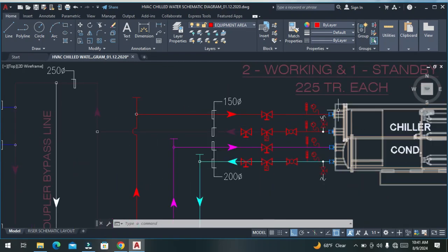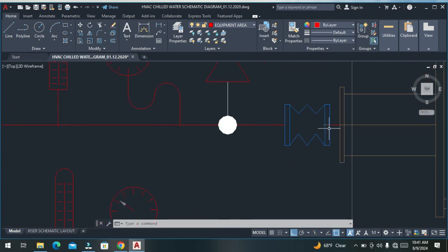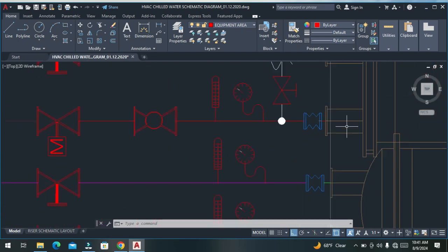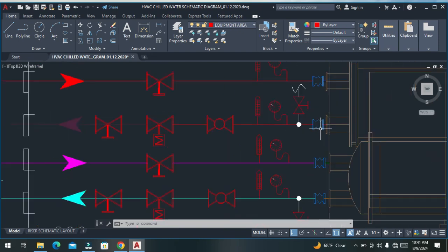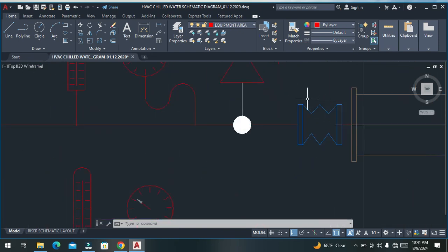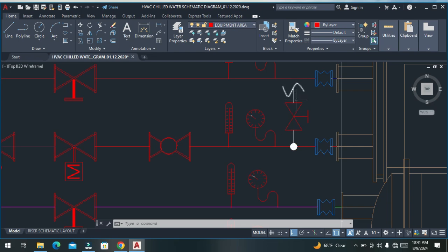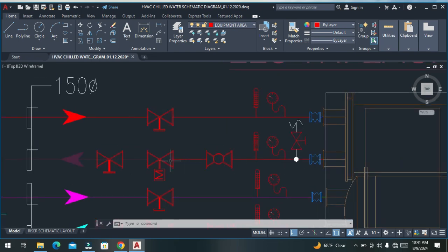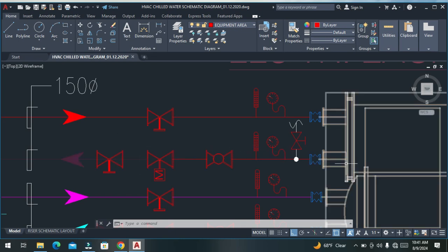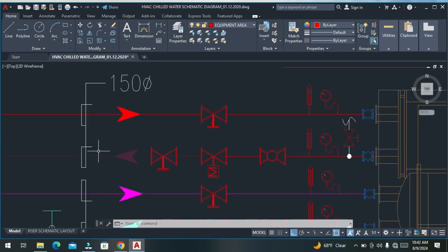If we talk about its piping, this is the outlet connection of the evaporator, from where the chilled water goes out. This is the flexible connector, or bellow. Then here we have a drain point of this outlet line, the supply line towards our HVAC units like FCU, AHU, TFA. FCU means fan coil unit, AHU is air handling unit, and TFA is treated fresh air unit. So this chilled water will go to the FCUs, AHUs, all HVAC units.